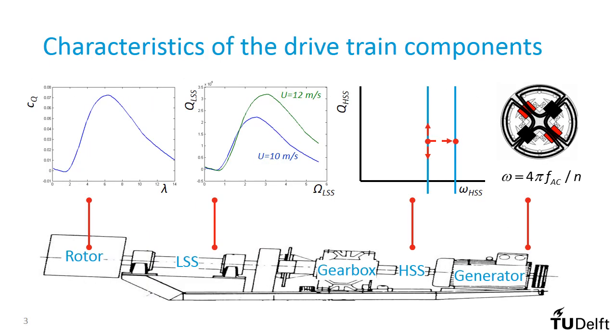Here you see a recap of the torque-speed characteristics of the different components. Neglecting losses in the main bearings, the aerodynamic CQ-lambda curve can be directly translated to the speed-torque curves in the low-speed shaft. Similarly, the speed characteristics of the generator can be directly translated to the speed-torque characteristic in the high-speed shaft. However, the speed and torque levels in the two shafts differ several orders of magnitude, due to the separation by the gearbox.